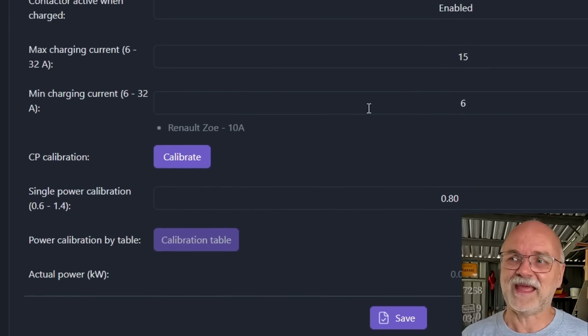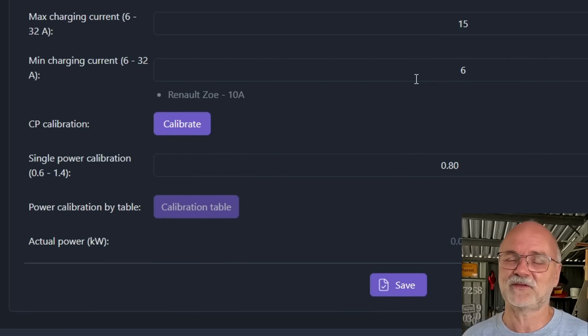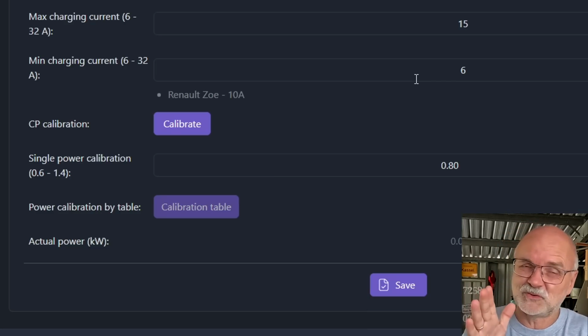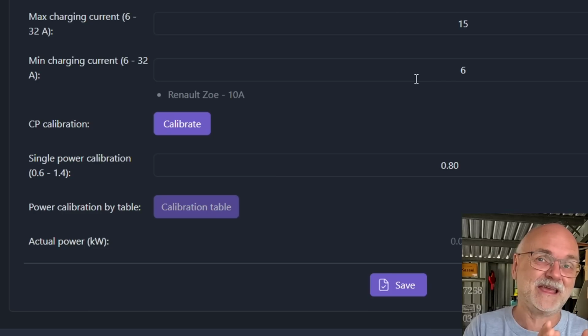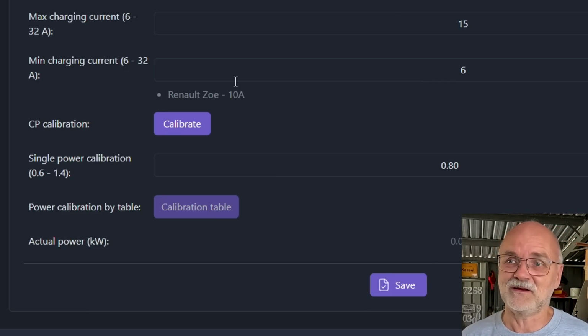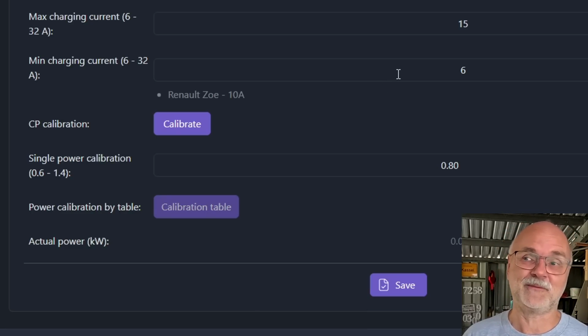We can also set a minimum charge current, which is important for the auto mode of the charging station. This is the minimum charging current your car can do. The Renault Zoe, for example, can only charge with a minimum current of 10 amps, but the Aura goes all the way down to 6 amps, which is fantastic, and we use this quite often.